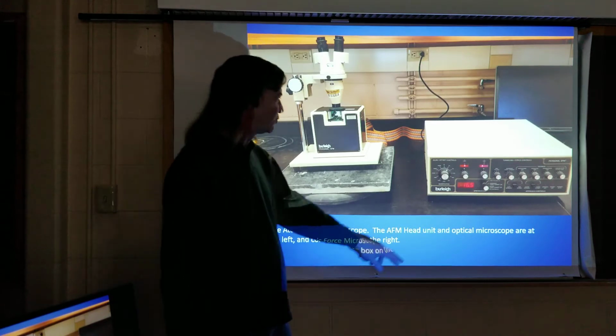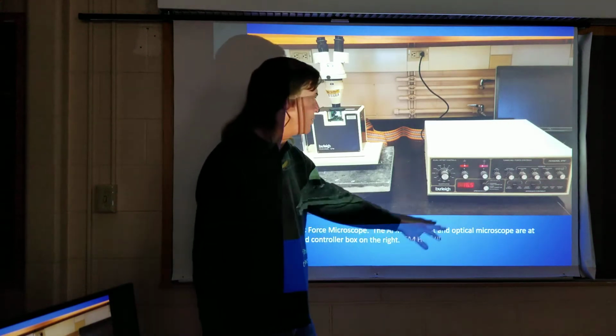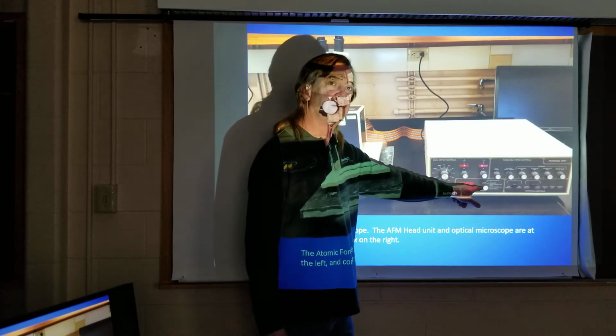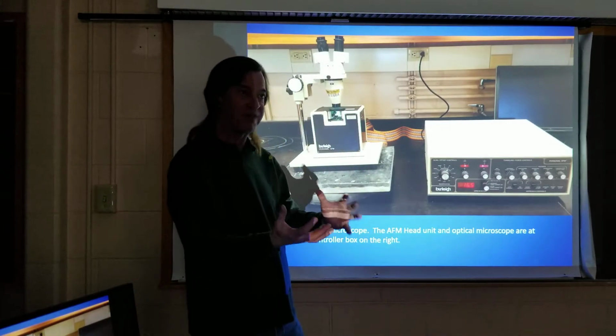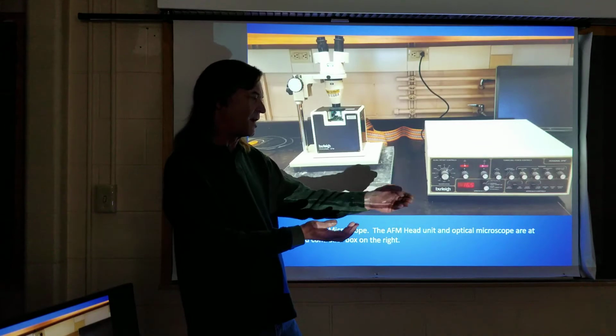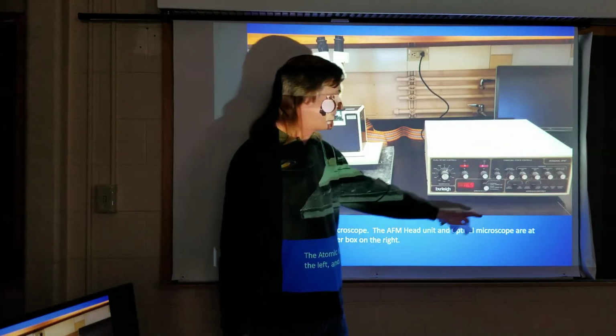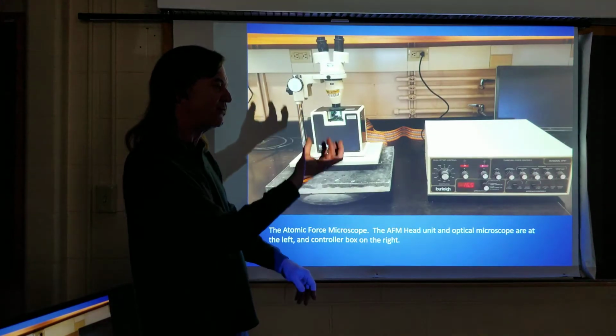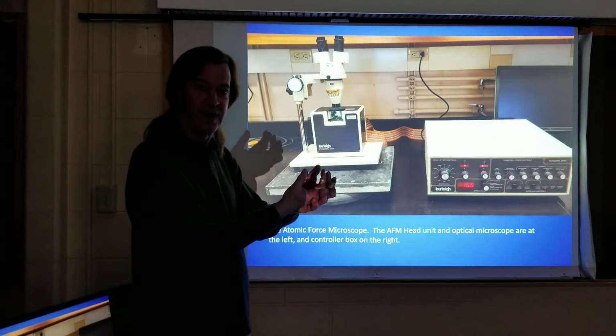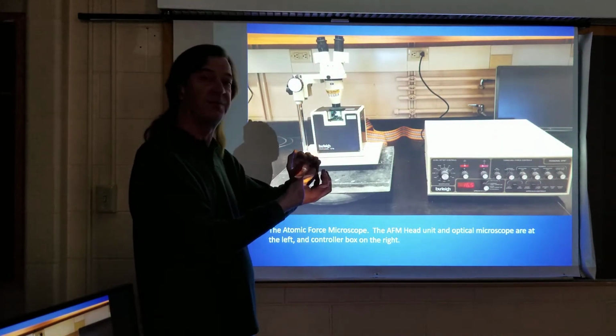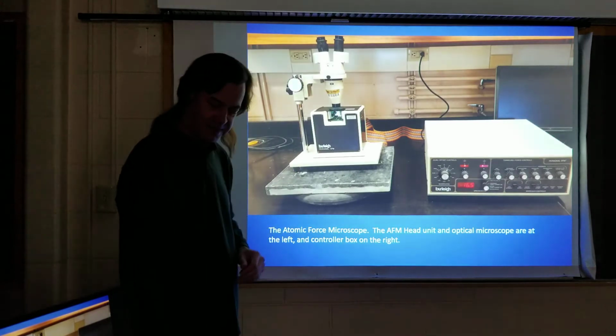And then there's this controlling box, and on here we can do all the things like adjust the magnification level and set our actual force. It tries to keep the same force as it scans over, so it's not scraping into it. And we've got the various feedback that it moves. In this case, the sample moves up or down with the piezoelectronics to keep the same force from the tip to the actual sample it's measuring.